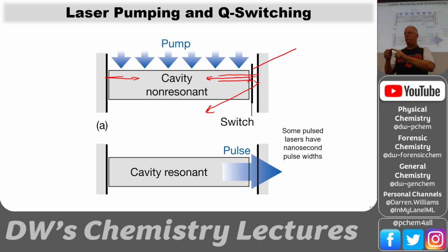And now it burned his thumbnail for sure, and that's bad enough. But he happened to be looking down to see what he was doing, and the laser hit the thumbnail and hit one of his eyes and just burned a big spot on his retina. So he was blinded in one eye in 10 nanoseconds. So that's how dangerous it can be. And so he should not have been aligning the laser at full power. He should have cut the power back and disabled the Q switch, and everything would have been fine.